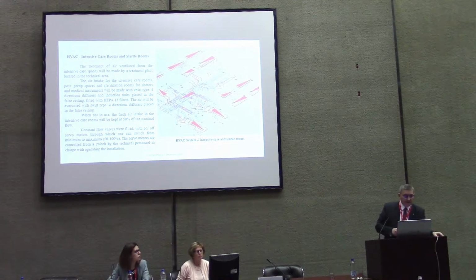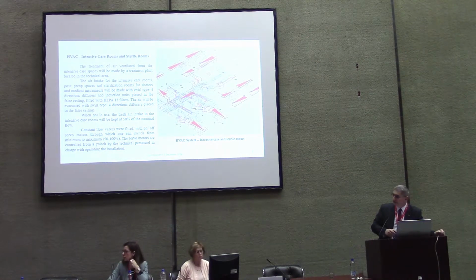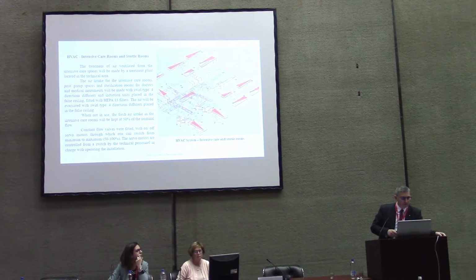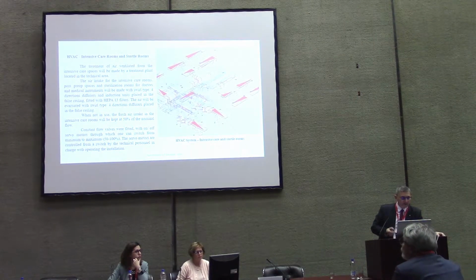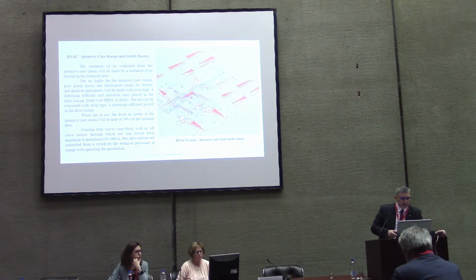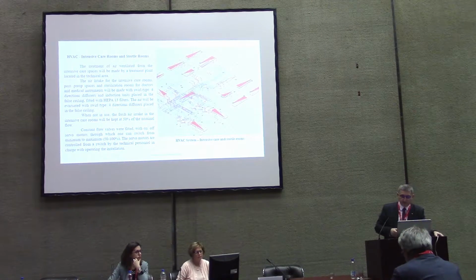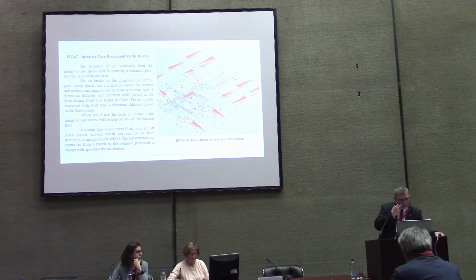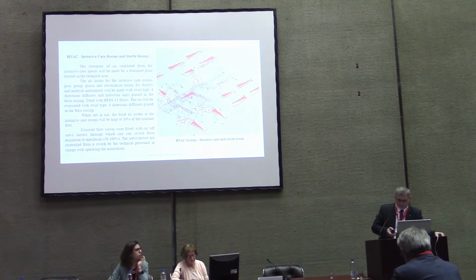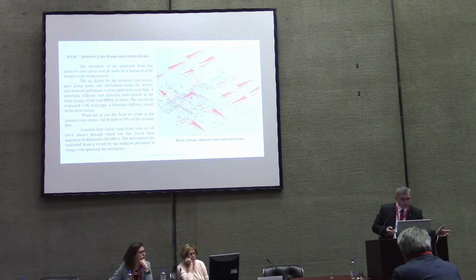The HVAC for intensive care rooms and sterile rooms: the treatment of air ventilated from the intensive care space will be made at a treatment plant located in the technical area. That means we have an air handling unit special for this area. The air intake for the intensive care room, pre and post-operatory space and sterilization room for doctors and medical instruments will be made with Swirl type 4-direction diffusers and induction units placed in the false ceiling. We have chilled beams systems and ventilation systems in the intensive care rooms with HEPA filters in each of them. When not in use, we will also keep this area at 50% of the nominal flow.